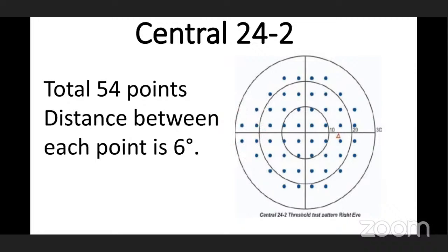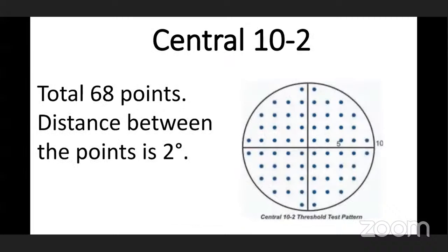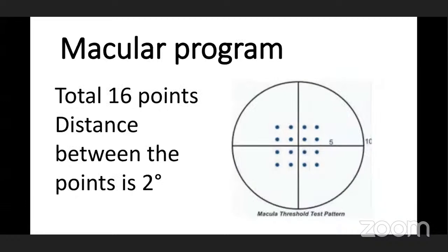Central 10-2 has a total of 68 points, with 2 degrees between each point — used when there is any suspected central scotoma. The macular program tests from center to 5 degrees of visual field area, with a total of 16 points and 2 degrees between each point. It is used to test the macular region.